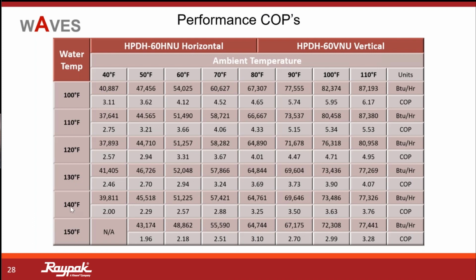So ambient air temperature and our supply water temperature: the lower we can make our water temperature and the higher the ambient air temperature available, the higher that efficiency. And this is a big driver in our engineering community to ASHRAE standards. They need to be above a certain threshold. So again, in the Sun Belt, in warm climates where we have high ambient air and moderate water temperatures, we can get into some very healthy production, right? So we said earlier that a 60,000 BTU unit, well, that's at a given ambient air temperature and water temperature. But if I can get into lower water temperatures and higher ambient air, now look at my performance. I'm doing a very good percentage more in production for harvesting those BTUs. So again, that ambient air temperature is a big factor in design for how much production you can actually see.